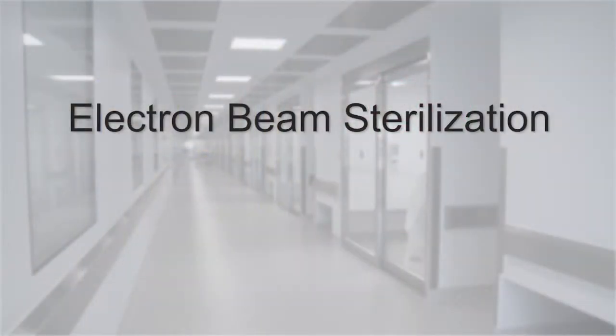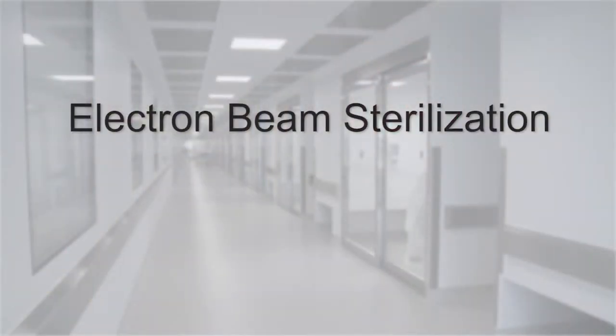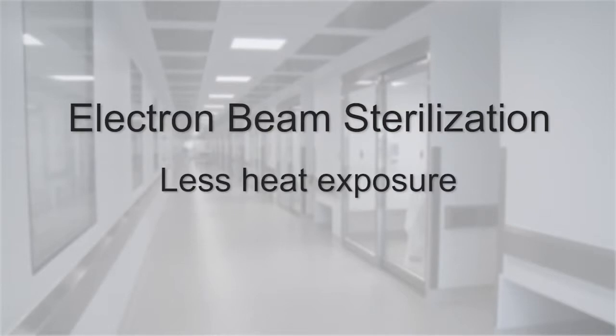There are several advantages. First of all, electron beam sterilization can occur within a matter of seconds versus gamma radiation, which usually takes about 5 to 6 hours. During that time, heat can be generated within the tissue as well as free radicals. Both of those elements can damage the collagen structure. So by minimizing the time with electron beam sterilization, you minimize the potential exposure of the tissue to those harmful elements.